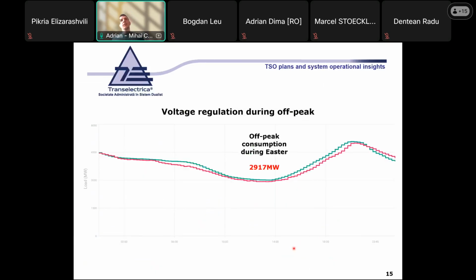Regarding voltage regulation, as you saw earlier, we have quite some power installed at the prosumers' level. This is hiding the vertical load of the transmission grid, which ends up causing low-loaded transmission lines. These low-loaded lines produce a lot of reactive power, which impacts the balance of reactive power, so we end up with really low loads and quite high voltages.